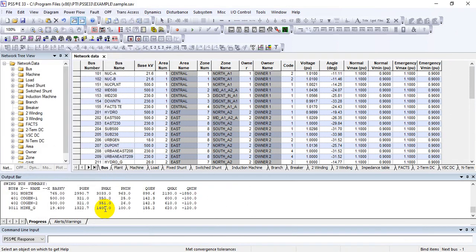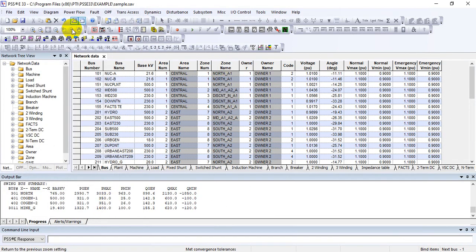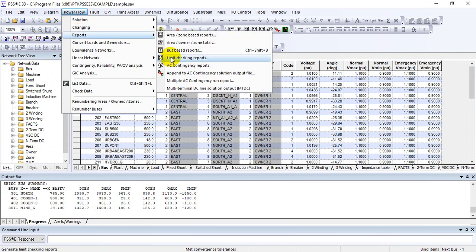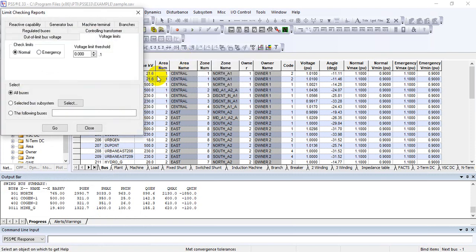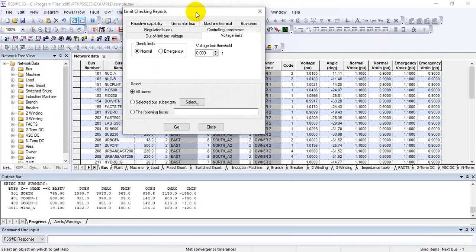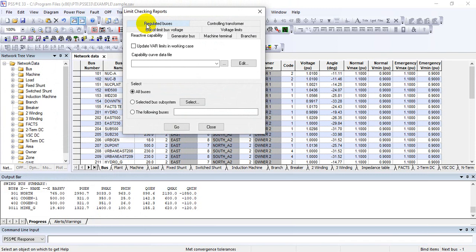After performing the solution, you can check the report. Under the Power Flow section, go to Reports and press Limit Checking Reports. In Limit Checking Reports you can see there are different options available. The first one is the Reactive Capability Report — for that you need to provide the reactive capability curve for each generator, and based on that you can find different out-of-limit buses with respect to reactive capabilities.